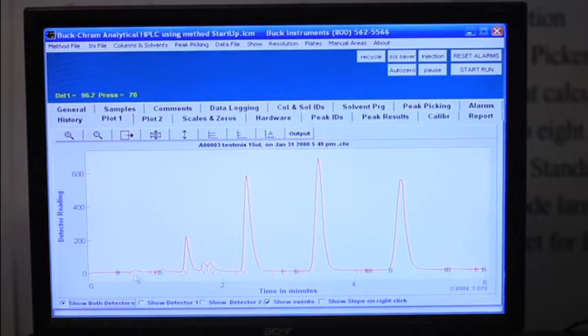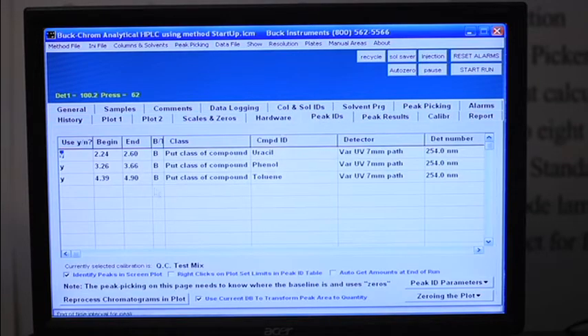Now that we've acquired our data and we have a chromatogram, the next step is to identify the peaks of interest. Navigate to the peak ID table, the peak ID tab, and you'll notice we already have 3 components in here. We're going to use these 3 components to label the peaks on the screen. Go down to the box that says right clicks on plot set limit to peak ID table and check it off.